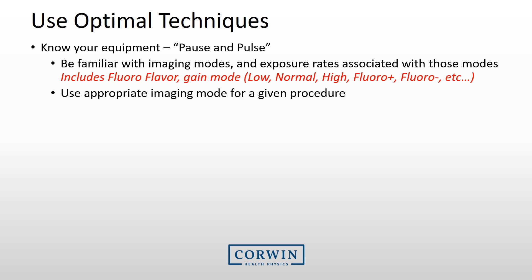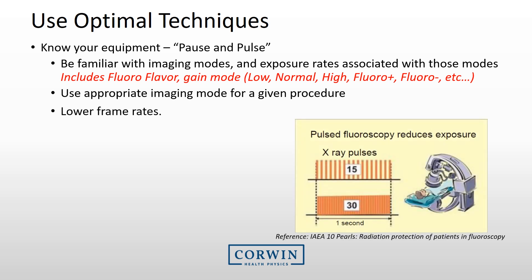Within the fluoro modes, you may be able to select the frame rate for fluoro, cine, and digital acquisitions. In most cases, a lower frame rate leads to lower radiation exposure rates. Use the lowest frame rate possible for that given procedure.